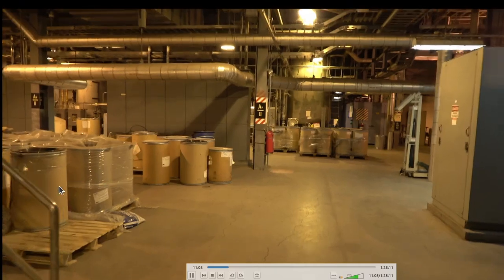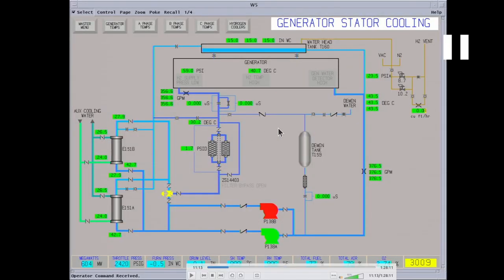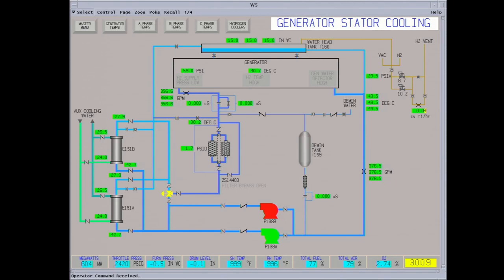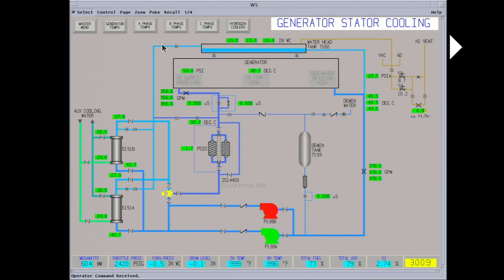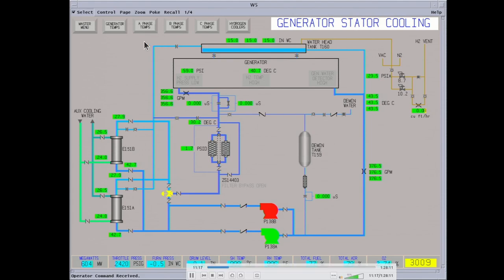This is an exciter transformer and control — it's a static exciter, so it uses a rectified voltage to control the generator voltage. Here's the demin system — older plants use demin. Here's the generator stator cooling — this is unique in that you use water in your generator windings for cooling. It has to be very pure, so it has its own resin bed. You get no conductivity. The water is fed up there and have Teflon tubes that feed each winding to minimize any leakage of current. This helped the generator load quite a bit as far as cooling goes.